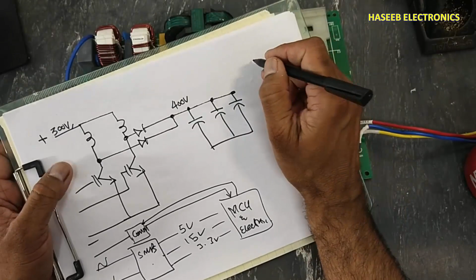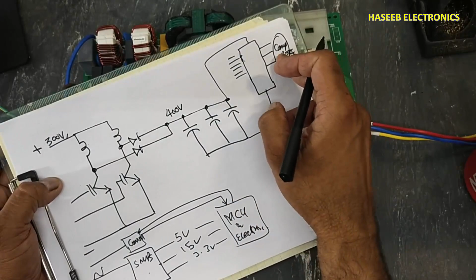We have 400 volt DC here on these capacitors. Here we have the IPM, Intelligent Power Module. Basically it is a set of 6 IGBTs with a driver IC. It will receive 6 commands, U, V, W, and it will receive this voltage and provide 3-phase to the compressor. The same set is used here for the outdoor fan.